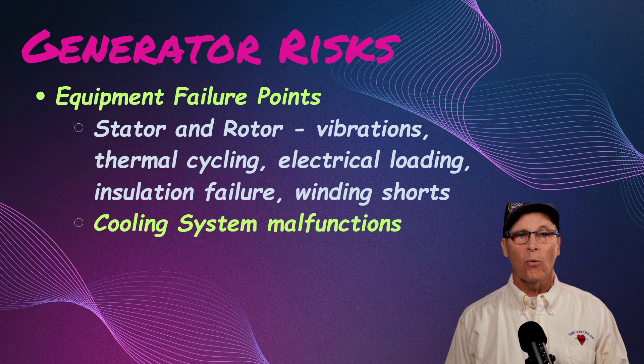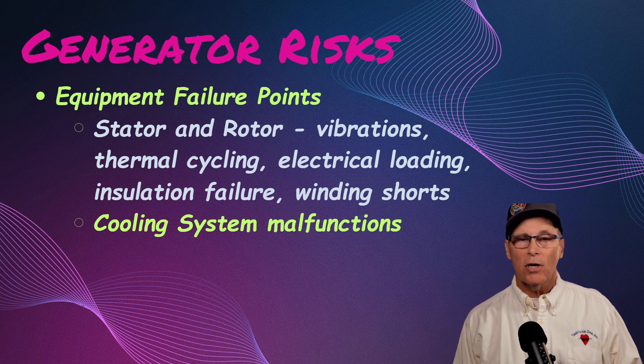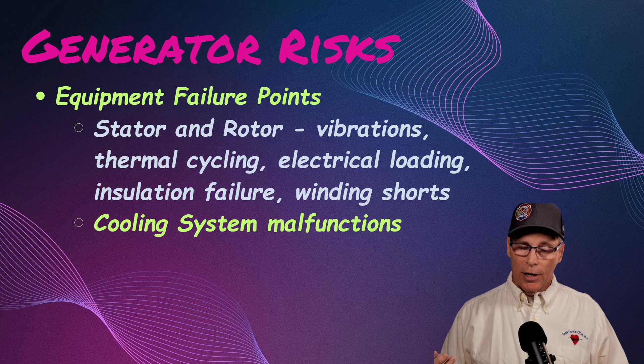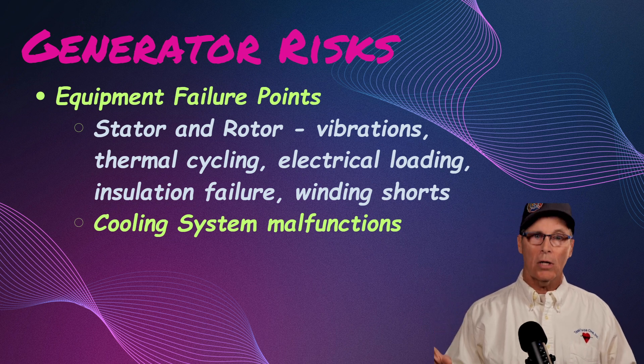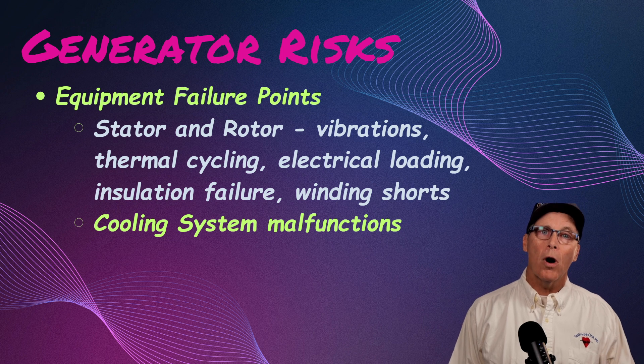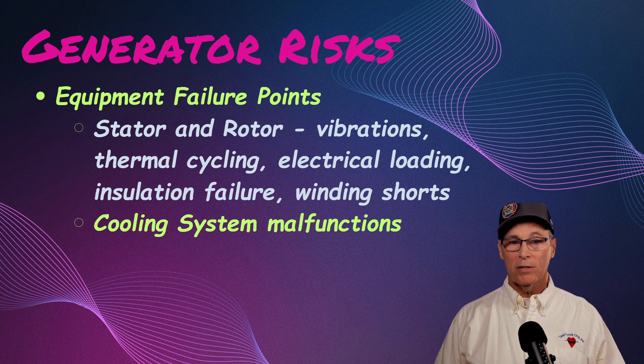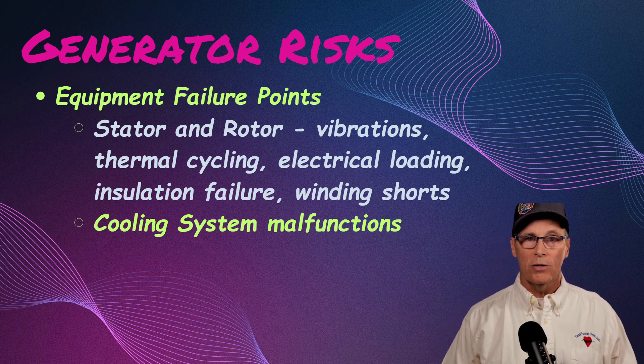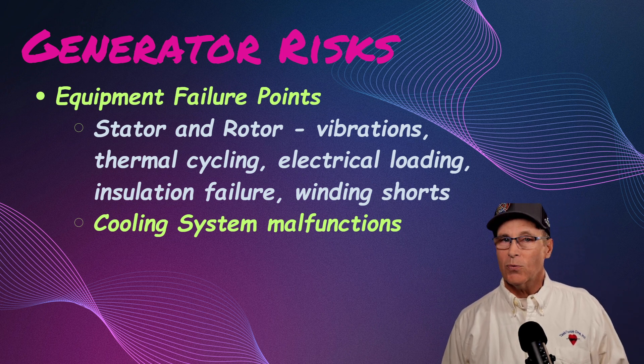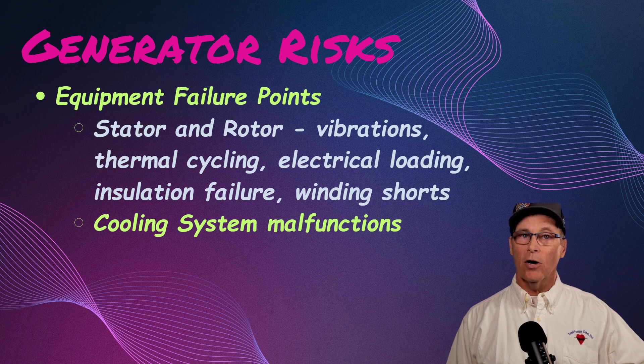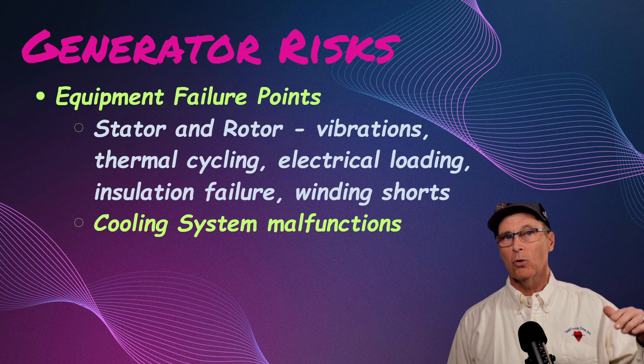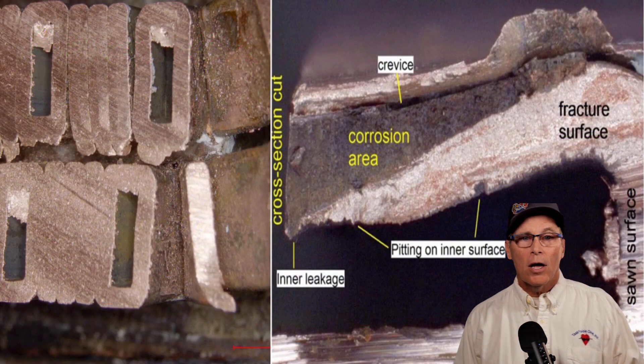Cooling system malfunctions — I've seen air-cooled generators where the air cooler is just a water radiator, like in front of a car. They don't last forever. In one case, the cooling system suddenly failed, leaking water into the unit. The adjuster tried to exclude coverage, arguing everyone knew the cooler was damaged and no maintenance had been done. But the generator was running fine the day before — only the cooler needed to be fixed. You can exclude the cooler, but you can't exclude the repair to the generator. We won that one.